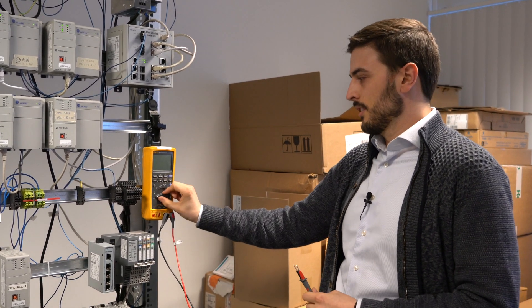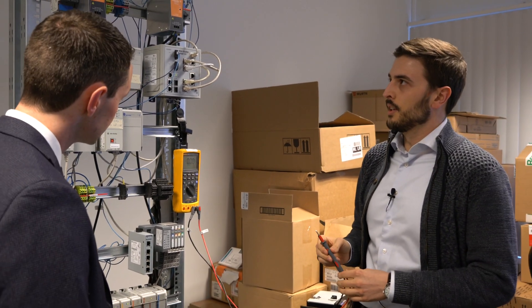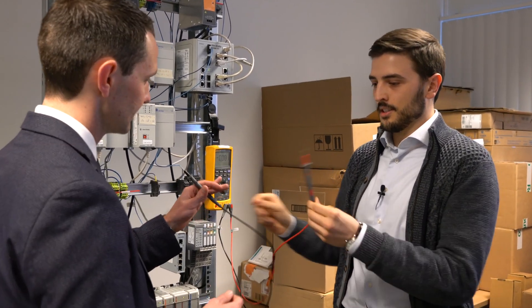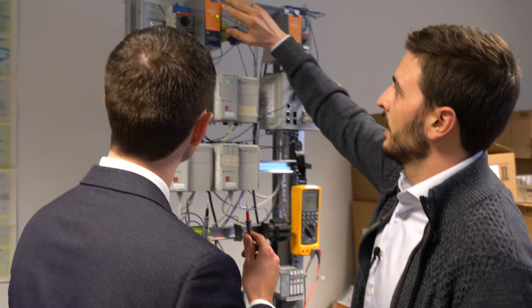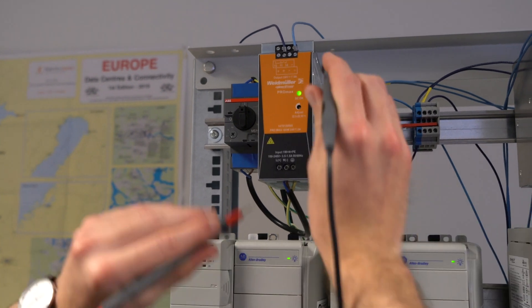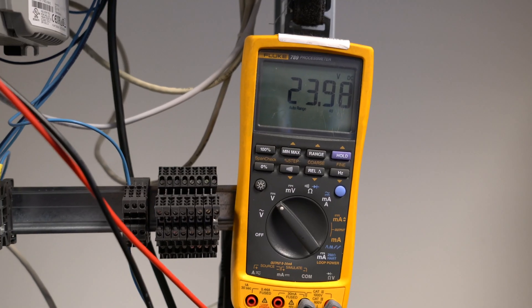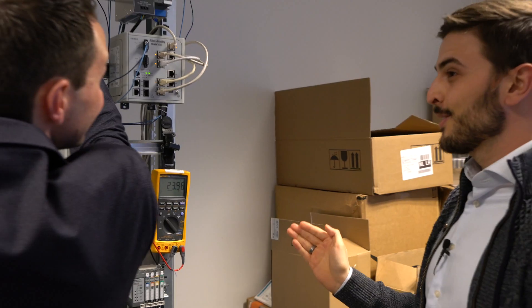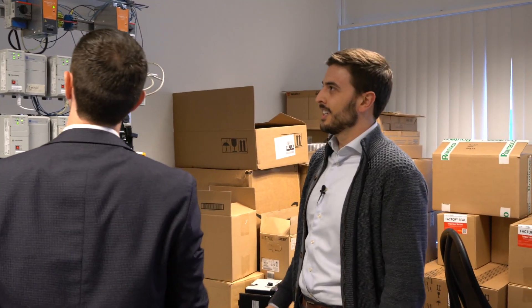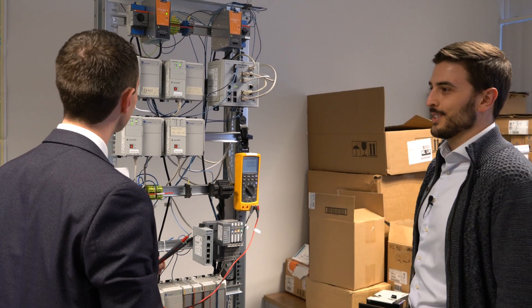This here is a multimeter. This is one of the important tools of electrical engineering. This is the negative lead, this is the positive lead. So if you just touch the negative lead here — the black one — and then touch the red one here, we should see 24 volts. So now we know our power supply is working. That seems very simple, but whenever you're doing testing and commissioning on site, that's always a good first thing to check. If you're ever wondering why your device is not on, that's a good place to start.